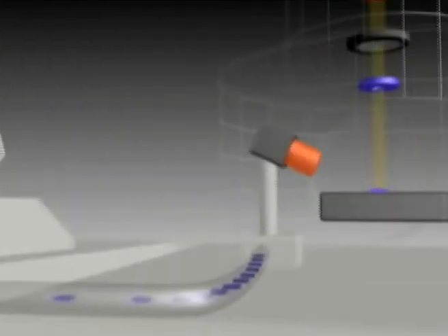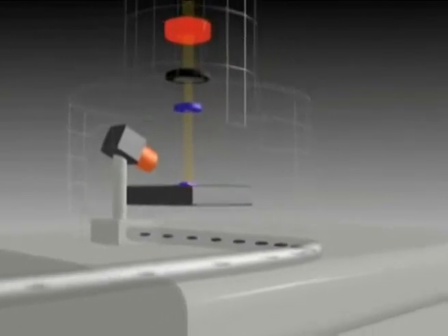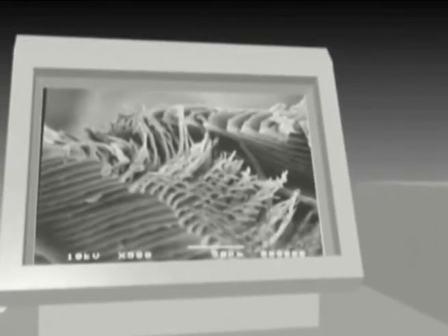This reflected signal is picked up by the electron collector close to the specimen and is amplified and displayed on a cathode ray tube. Thus, the electron beam in the microscope probes the details of the specimen surface by screening it line by line, and the secondary emission produced by this probe is simultaneously displayed line by line on a television screen, building up a faithful replica of the surface detail of the specimen.